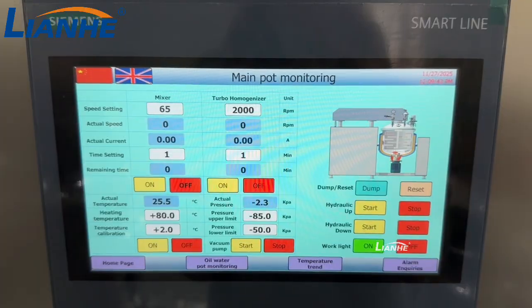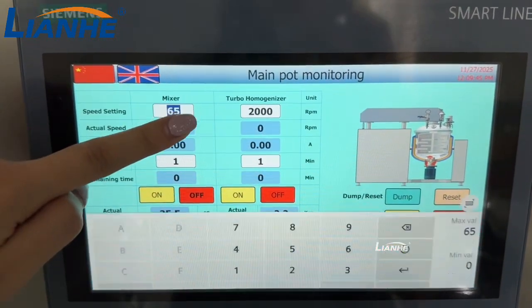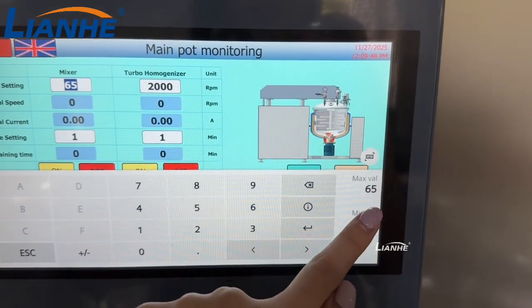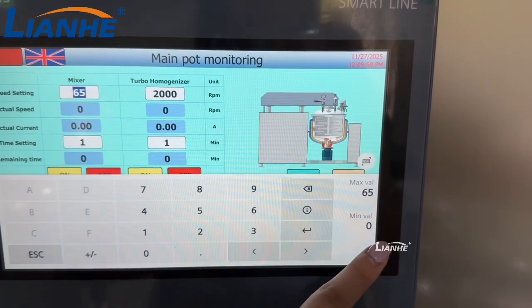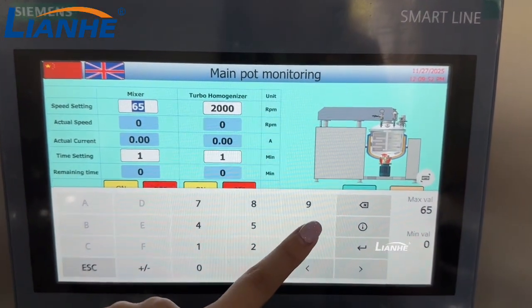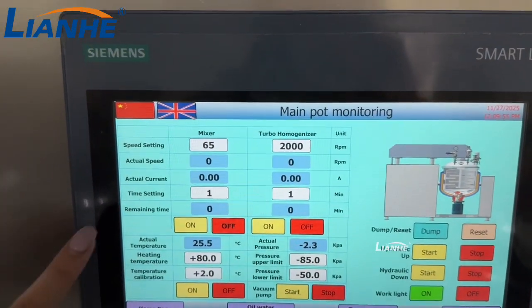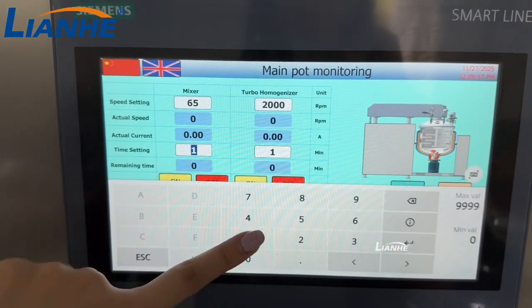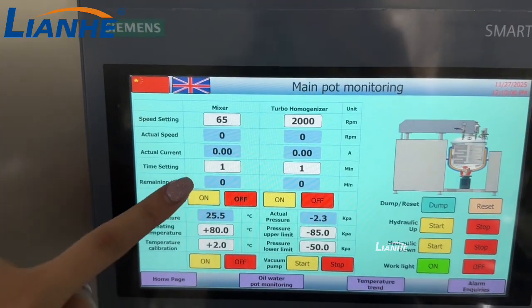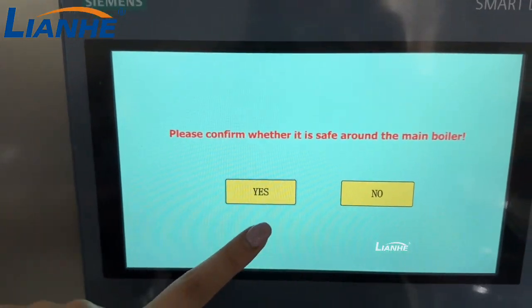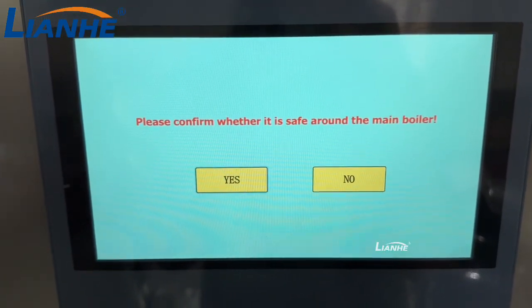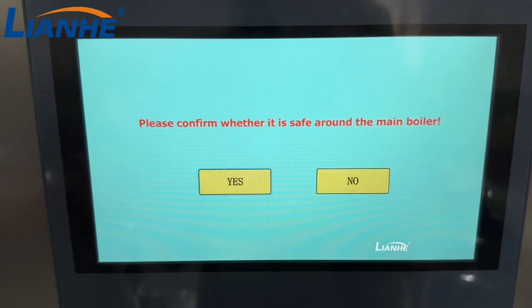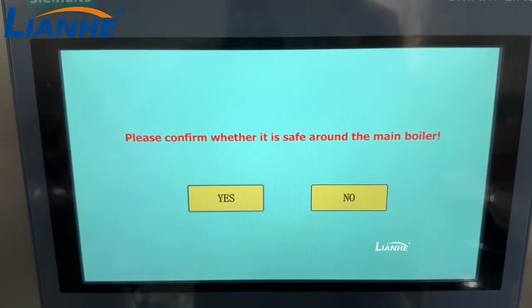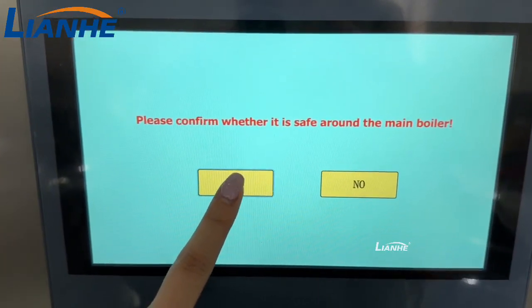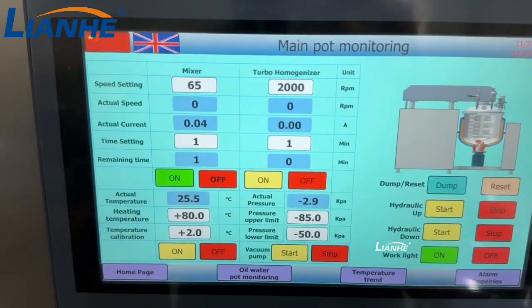Okay, and now we can test the mixing function, like the speed setting here. We have the maximum, like the 65 speed, and the minimum speed here. You can check, like 65. And then the time setting here, 1 minute to set. And then turn on the mixing function. And this is the confirm. You should make sure that the main tank is in the correct place, in the reset place. And then you can confirm yes. And then you can use the mixing function.